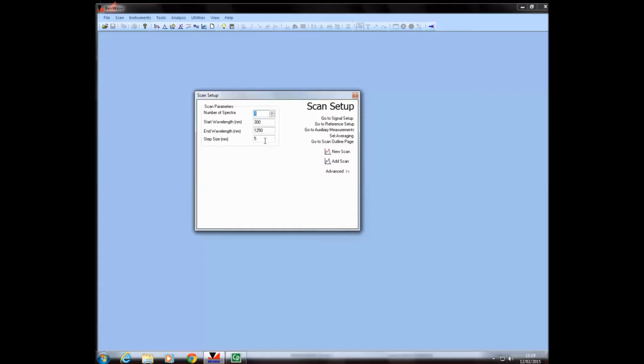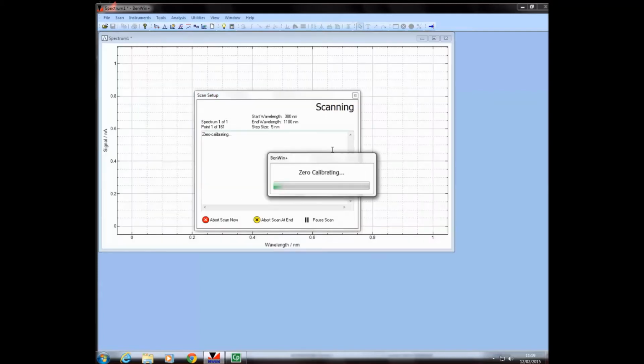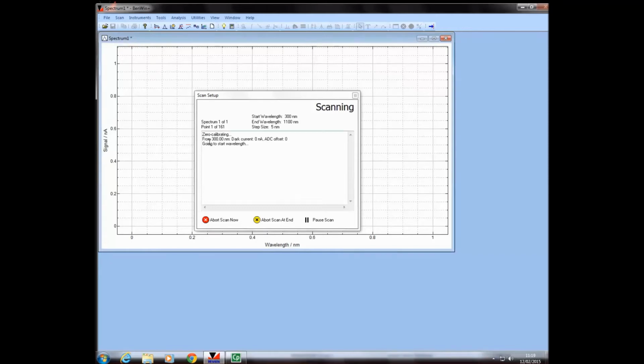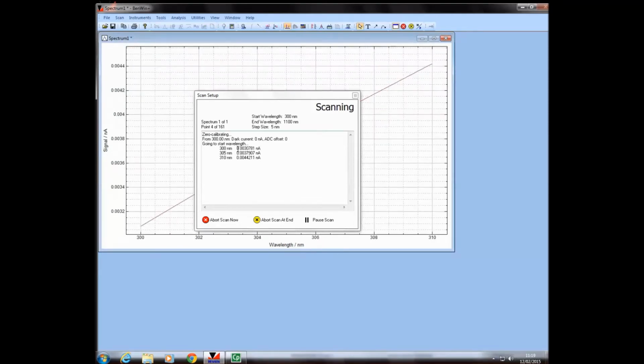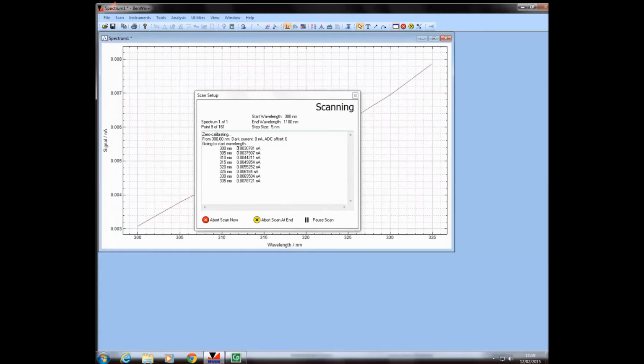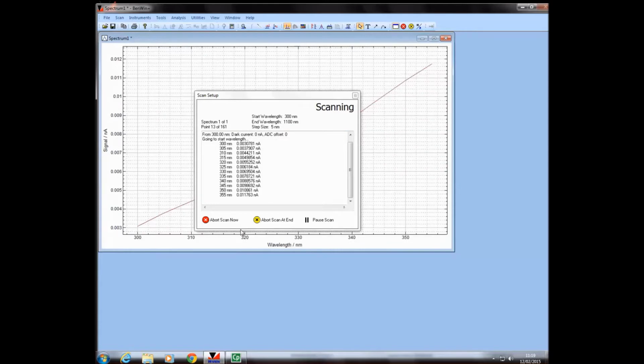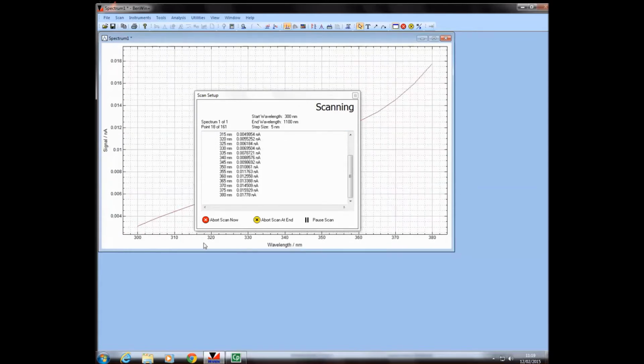The silicon reference device can be used over the range 300 to 1100 nanometers, over which we will scan for the present. It's good to check in advance that data correction is not selected. Data correction signals that the system is calibrated, which clearly when we're calibrating the system should not be the case. And we will hit New Scan. At all times during system calibration, the y-axis should read signal in nanoamps. The zero calibrate procedure places a shutter at the exit of the monochromator, allowing no light to the detector, and takes some offsets of the system. We will pick this scan up at the end of the measurement.